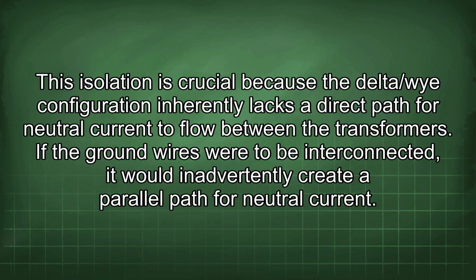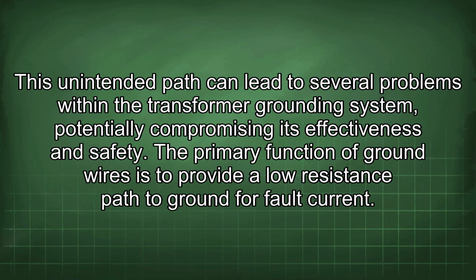This isolation is crucial because the delta/Y configuration inherently lacks a direct path for neutral current to flow between the transformers. If the ground wires were to be interconnected, it would inadvertently create a parallel path for neutral current. This unintended path can lead to several problems within the transformer grounding system, potentially compromising its effectiveness and safety.